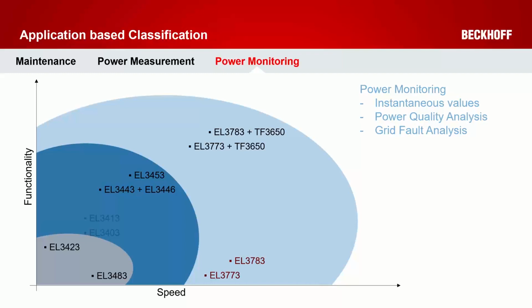So then we come to the power monitoring terminals. Here I have two candidates. One is the EL3773 and the other is the EL3783. They are designed for analyzing three-phase systems based on instantaneous values. Both allow simultaneous measuring of all 6 channels, that means 3 voltages and 3 currents, based on oversampling principles, with a resolution down to 50 microseconds. Together with the TF3650 PLC library, a full power quality analysis can be realized. Also, the raw values as part of the PLC dataset help to deeply analyze grid faults.